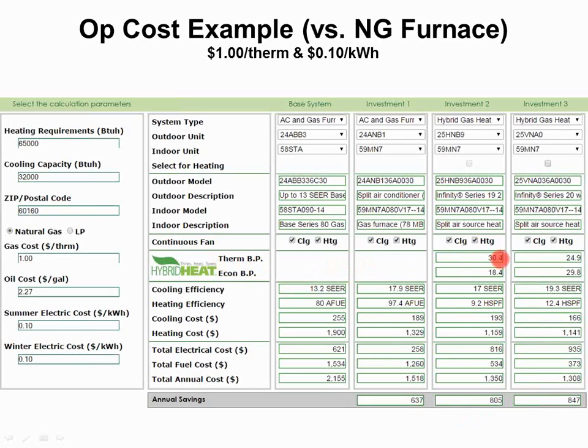In this case, it's 30.4 degrees. That means when it's below 30.4 degrees, this particular heat pump cannot do all the heating load by itself for this particular house. Somebody's got to help them out. In this case, the furnace is the one that's going to have to do it. It also calculates the economic break point. That means based on my utility costs of $1.00, when it gets down to 18 degrees and below, that's when the heat pump no longer financially makes sense and I should run the furnace.